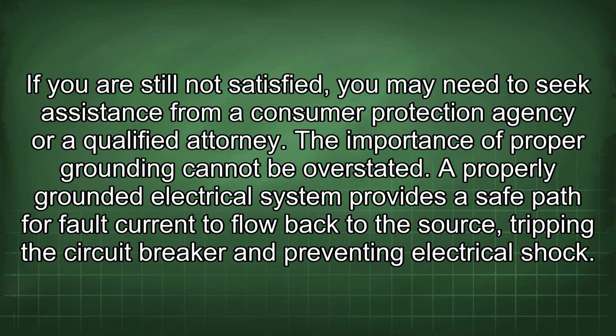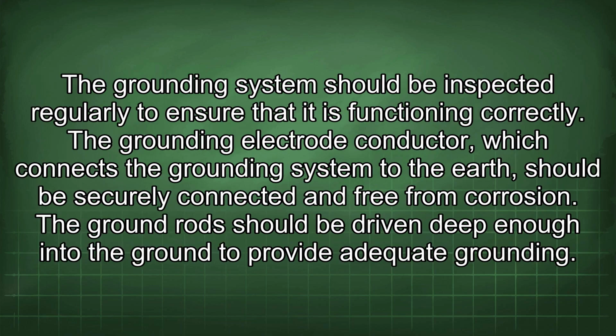The importance of proper grounding cannot be overstated. A properly grounded electrical system provides a safe path for fault current to flow back to the source, tripping the circuit breaker and preventing an electrical shock. The grounding system should be inspected regularly to ensure that it is functioning correctly.